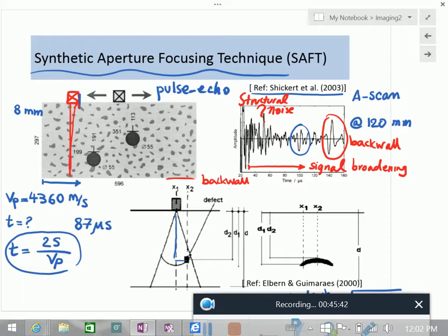How come we didn't see that in the stuff that we did in the lab? How come we weren't excluding any of the really early stuff that we saw in our signals? But you weren't working in the near field. You had like 3 inches. We will measure the near field of the transducer. You see it's only a couple of millimeters. And then you see those ripples, those small things in the beginning, the noise you have.